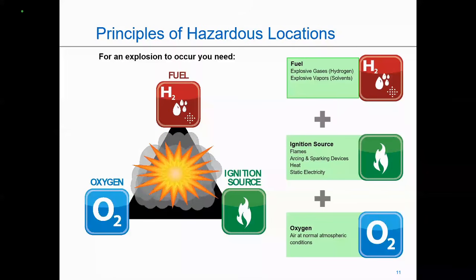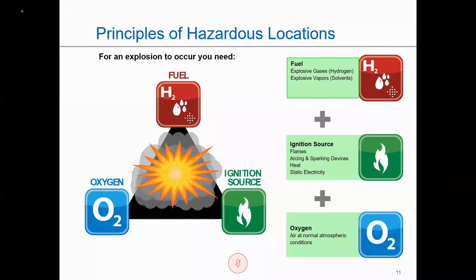Now, in order to have explosion, we need to have the 3 elements that make up the combustion triangle. We need to have our fuel. So in this case, it would be the flammable gas, liquid, or vapor. We need to have an oxidizer, and we also need to have an ignition source. And these elements need to be in proper proportion for there to be an explosion.